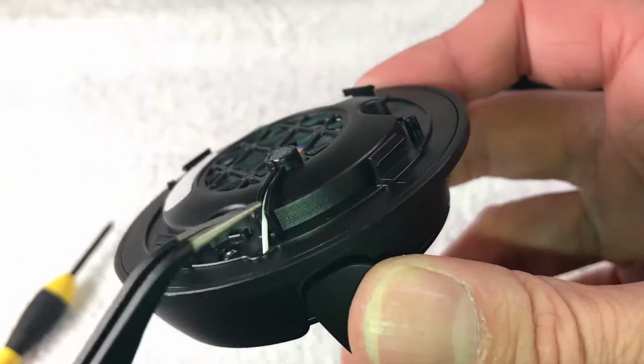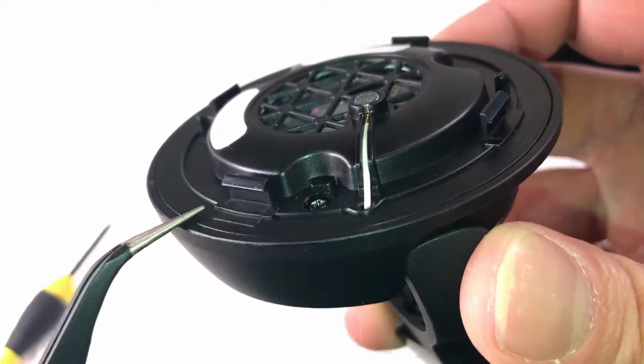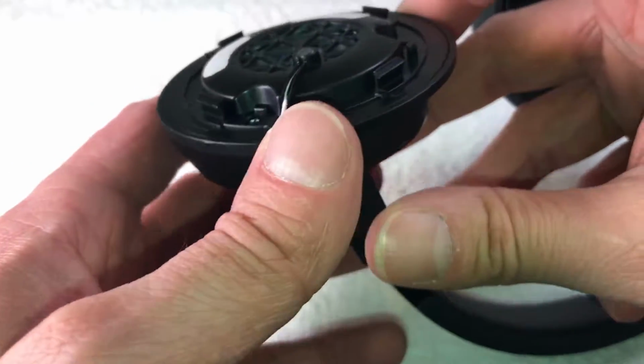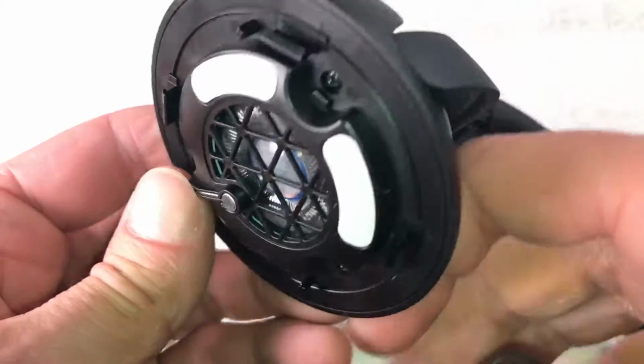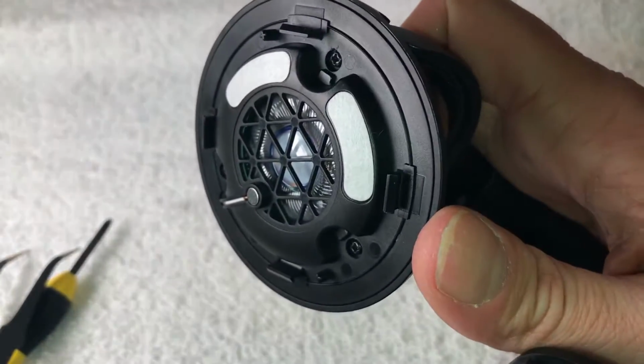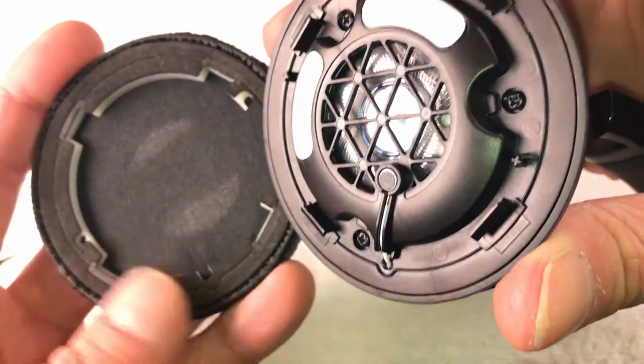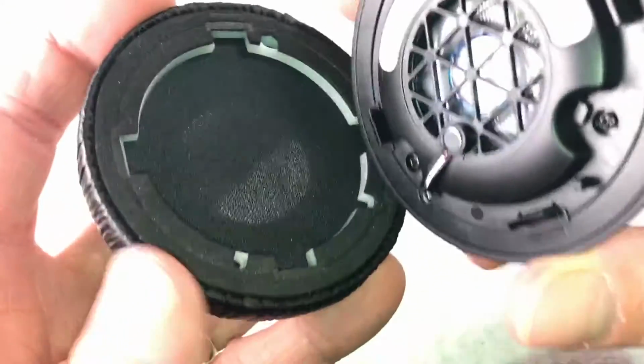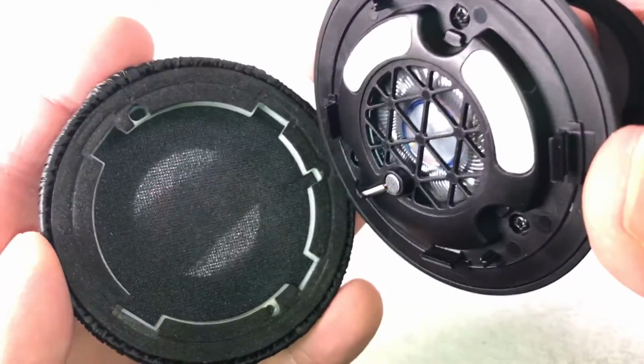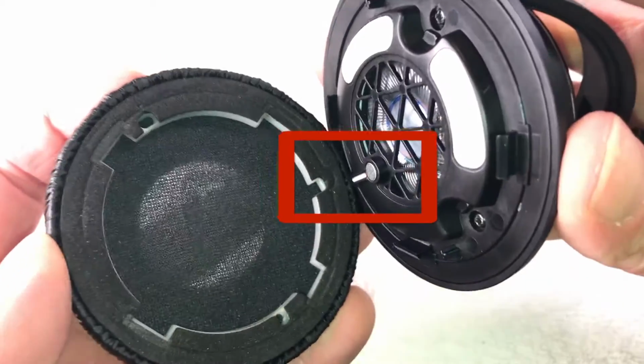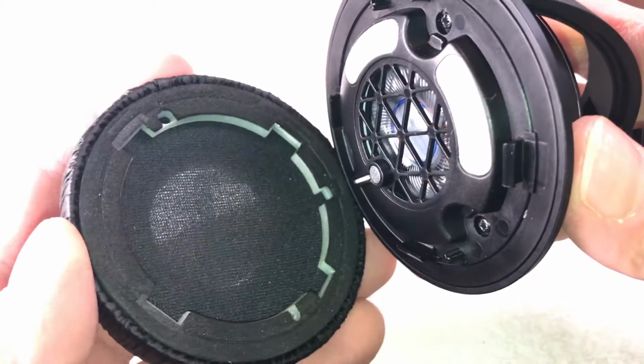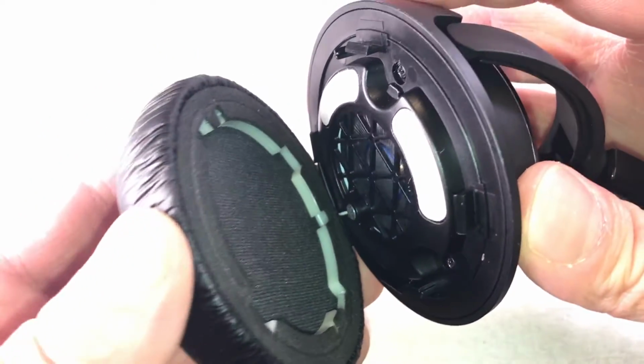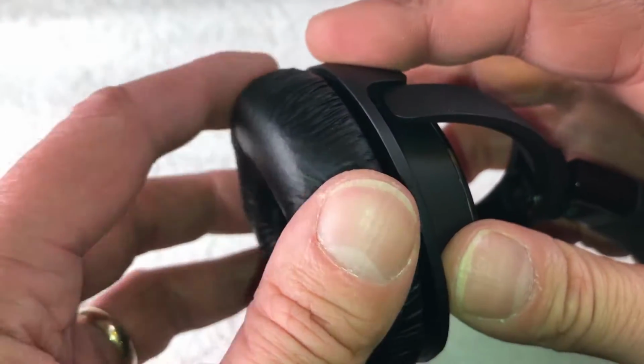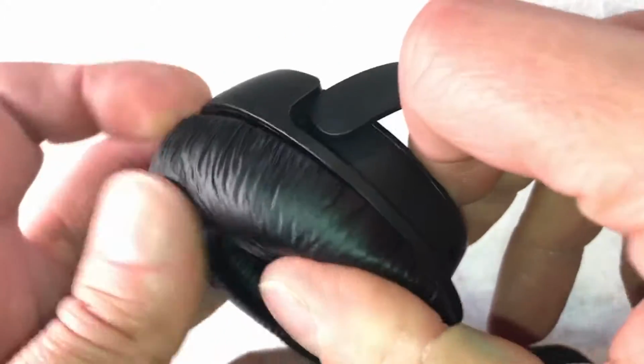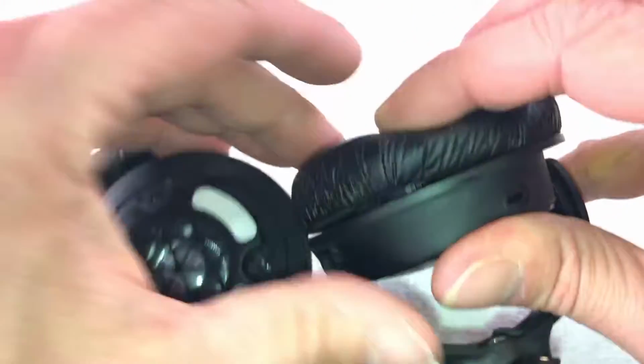And then we just install those three screws that we removed earlier, and check that this is all nice and flush. When it is, we can put the ear cushion back on, and also check that the little cutout on the cushion and the wire line up. When they do, you can just put the ear cushion on top and press it into place so that it clicks.